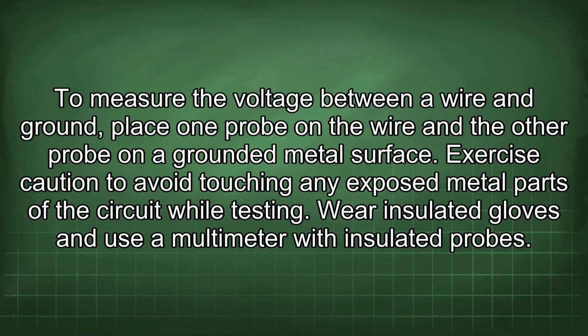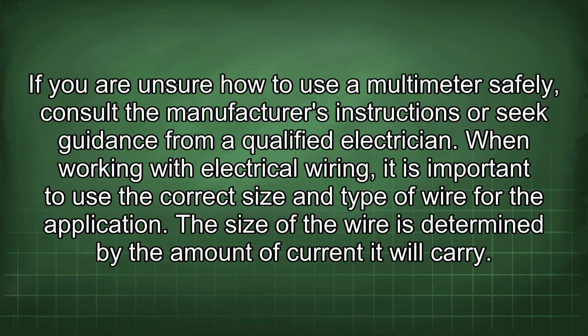To measure the voltage between a wire and ground, place one probe on the wire and the other probe on a grounded metal surface. Exercise caution to avoid touching any exposed metal parts of the circuit while testing. Wear insulated gloves and use a multimeter with insulated probes. If you are unsure how to use a multimeter safely, consult the manufacturer's instructions or seek guidance from a qualified electrician.